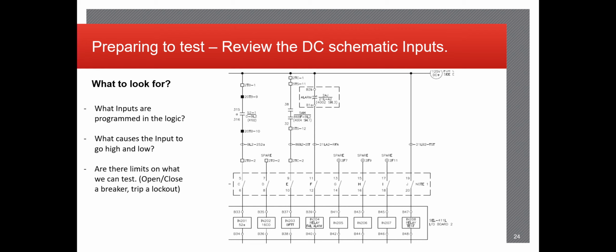The inputs, again: what inputs are programmed in the logic, making sure that when you operate this other equipment, it comes into the correct input. Is it labeled correctly? Is it going to show up on the SER as a 52A status? As well as what causes the input to go high and low, and are there any limits?